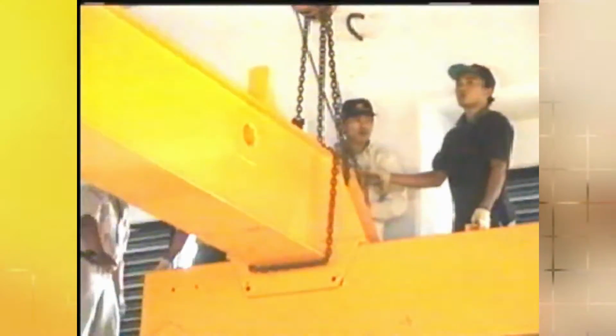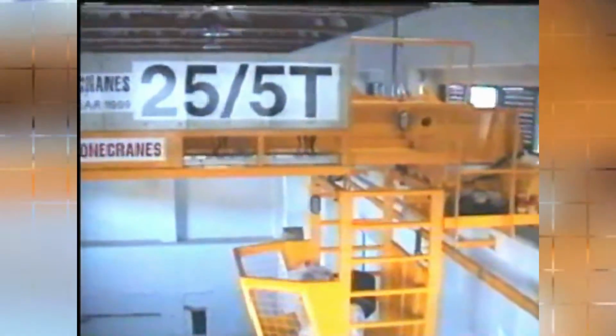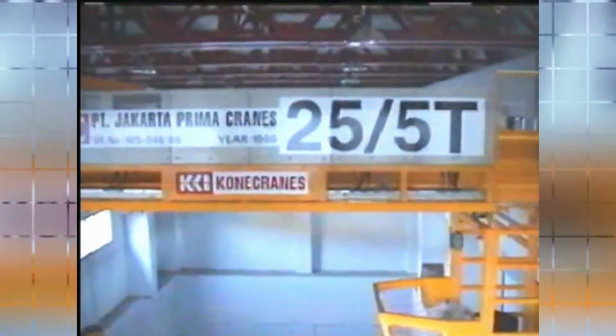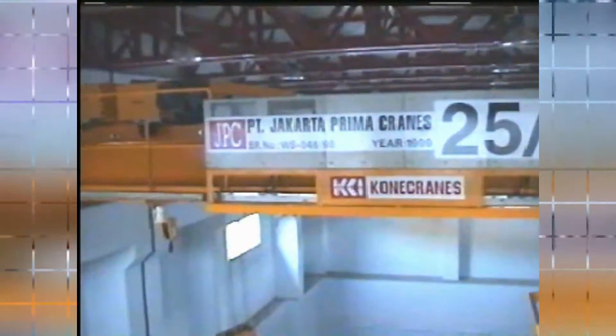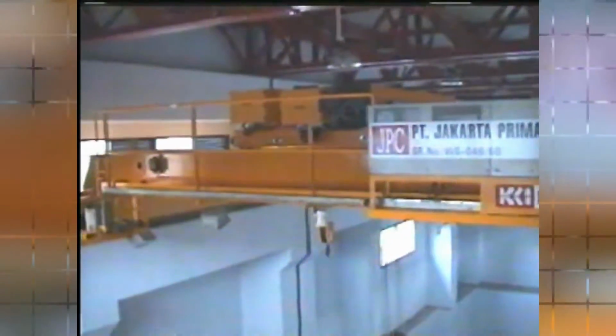The elevation of the bottom surface of the crane hooks at their highest position is at elevation 107.00 meters. The span, hook limits, clearances, and maximum lifts are compatible with the power plant arrangement and dimensions. Crane rails are 10.0 meters on centers. The total length of runway is approximately 25 meters and straight. The hoist shall raise, lower, and hold in any position a test load of 125% of its rated capacity. The second hoisting position shall raise this load, and it shall not lower in the first hoisting position. Trolley and crane shall travel at full speed or as directed along the full runway length with a test load of 125% rated capacity.